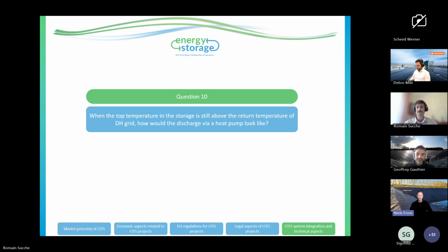That's quite simple, I think. We have to distinguish between whether the heat pump is cooling the storage or has an external heat source. In the first case, with an external heat source, you take the return water through the heat exchanger to the pit for preheating, and then through the heat pump condenser afterwards. You might have a small bypass for undercooling the refrigerant to get a better COP, but that's a technical detail. In the second case, where the heat pump is cooling the storage at the same time, the return water from the district heating network will first enter the evaporator of the heat pump, then the heat exchanger from the pit, and then end in the condenser of the heat pump.